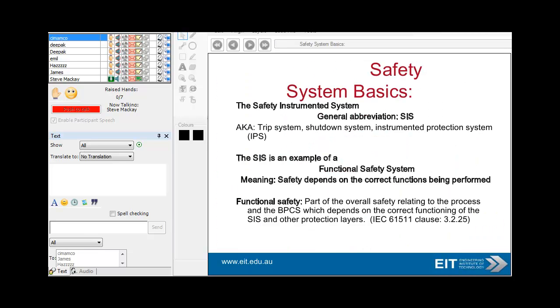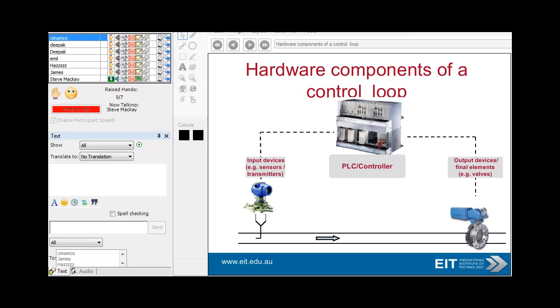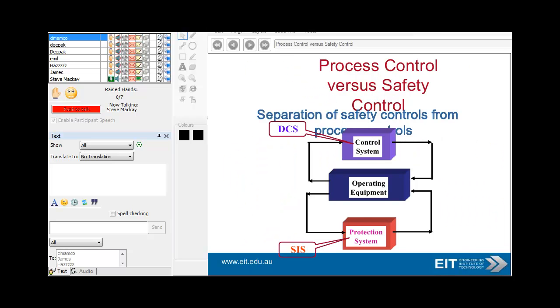A safety instrument system is an example of a functional safety system, meaning safety depends on the functions being performed correctly. The two standards used are IEC 61511 and IEC 61508. A typical control loop has information coming in from a flow meter — the process variable — through to a PLC controller or DCS, then a control device output as the manipulated variable.